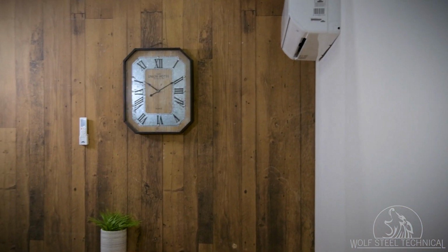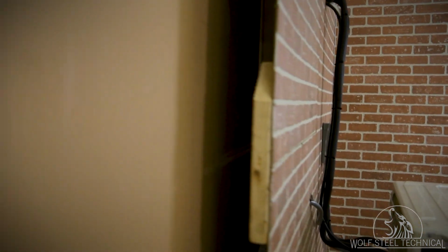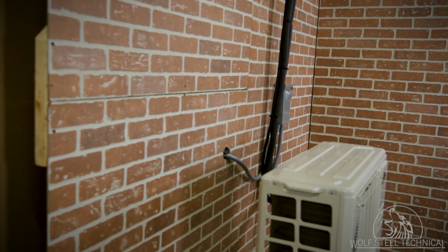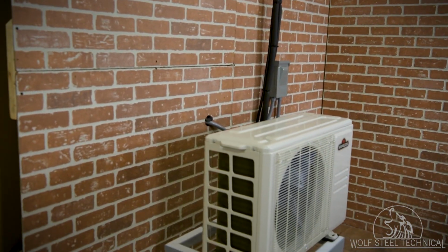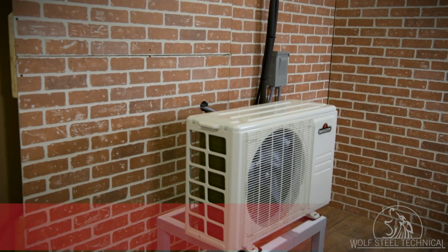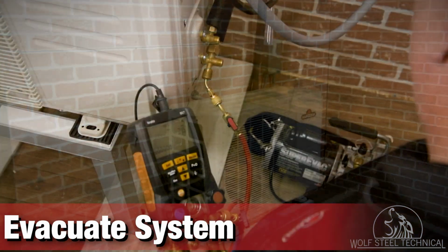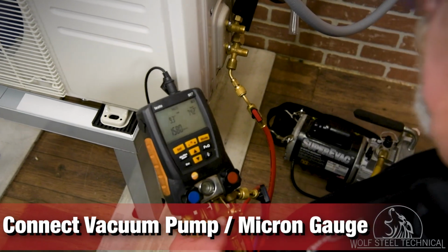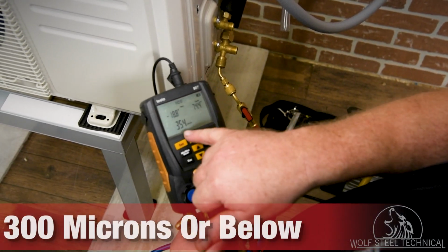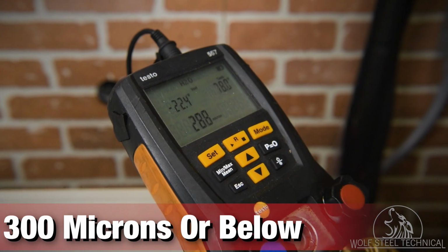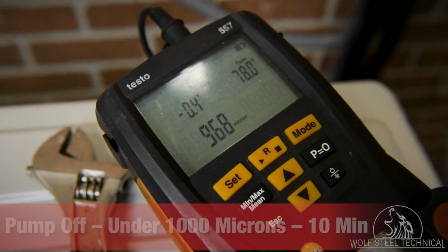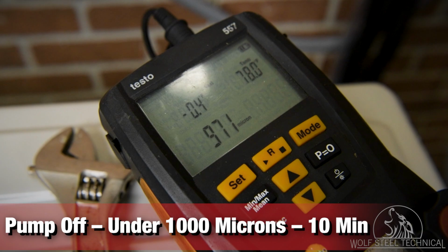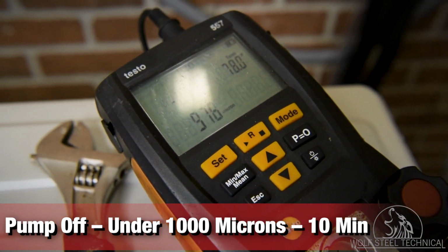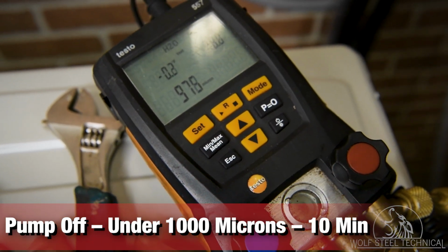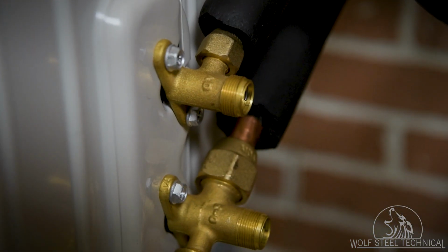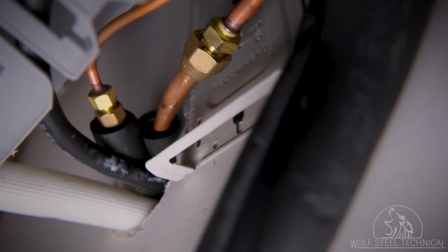Air and non-condensables in the system can cause abnormal rises in pressure, which can damage the unit, reduce its efficiency, and cause injury. To eliminate these issues from occurring, the system must be evacuated. To do this, connect a vacuum pump and micron gauge to the system and run the pump until the micron gauge reads 300 microns, or below. Turn the pump off and ensure the system can hold under 1000 microns for 10 minutes, as a double check for leaks. Should the system exceed 1000 microns, check all connections and ensure the vacuum process was performed correctly.